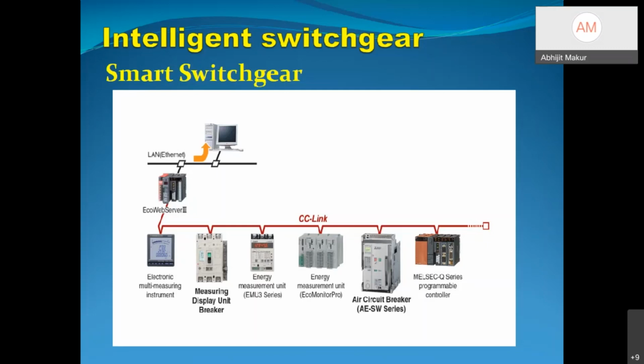We require reliable power 24 by 7, and at the same time we require quality power. So if any fault within the circuit breaker, the metering circuit, or the sensing equipment, CTs and PTs, is detected before the actual fault is initiated, that gives us time to go in for maintenance and divert the power during the shutdown period and get the circuit back into the system without the consumers being affected. So this is now the essence of what we require.